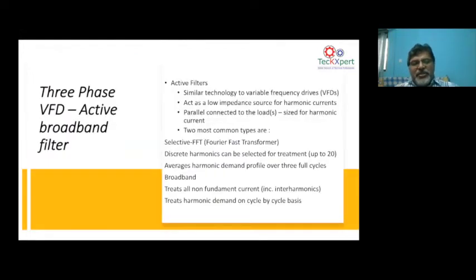See, now coming to the active filter. The very advantage of an active filter is that it can filter the harmonics without any fixed function like a passive filter, where you remove the 3rd, 5th, 7th. Here you can remove the entire harmonics as a broadband filter, or you can remove selectively the harmonics. So the advantage of an active harmonic filter is that it is a very simple device in terms of filtering harmonics. It's easy to install. It is just a shunt device.